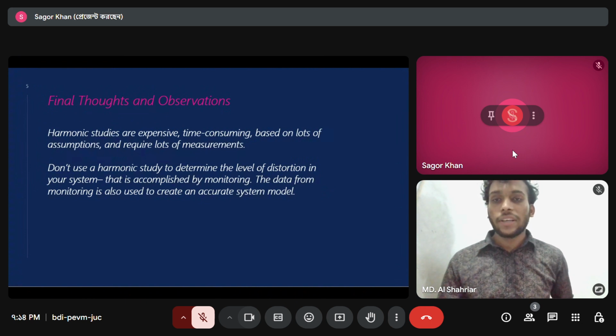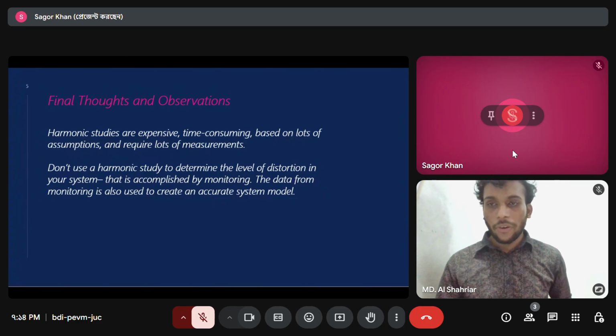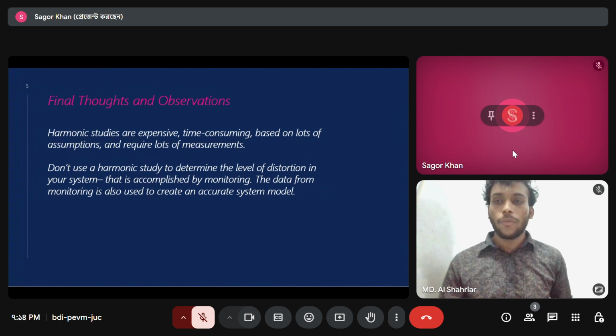Final thoughts and observations: harmonic studies are expensive, time consuming, and require a lot of measurement. Don't use a harmonics study alone to determine the level of distortion in your system; that is done through monitoring. The data from monitoring is also used to create an accurate system model.